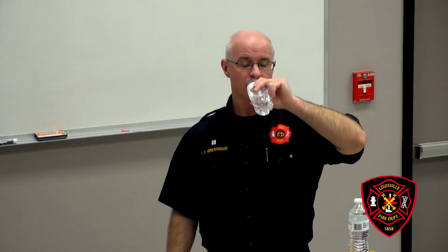Okay. Now, we need to make sure that before we do this, we also have our relief valve set, so that the guys don't feel the pressure from the hydrant on the end of their attack line. Okay, so once you get your intake open, now you're going to have water on your pump. You're going to be able to go around, potentially throttle down, and use less engine RPMs, because now we're using pressure directly off of the hydrant itself.